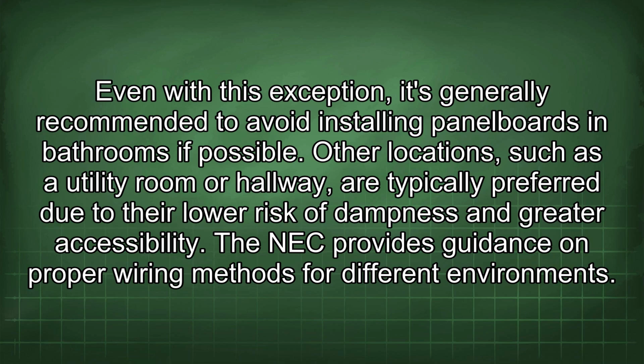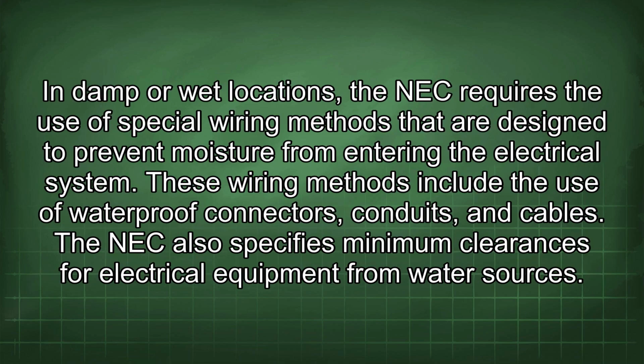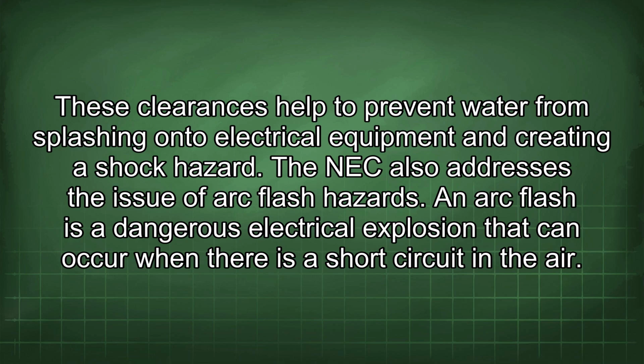The NEC provides guidance on proper wiring methods for different environments. In damp or wet locations, the NEC requires the use of special wiring methods that are designed to prevent moisture from entering the electrical system. These wiring methods include the use of waterproof connectors, conduits, and cables. The NEC also specifies minimum clearances for electrical equipment from water sources. These clearances help to prevent water from splashing onto electrical equipment and creating a shock hazard.